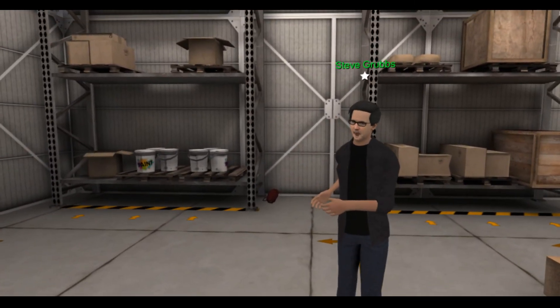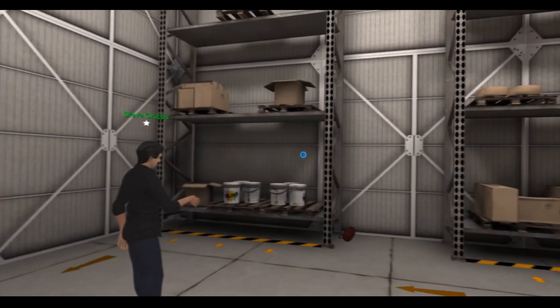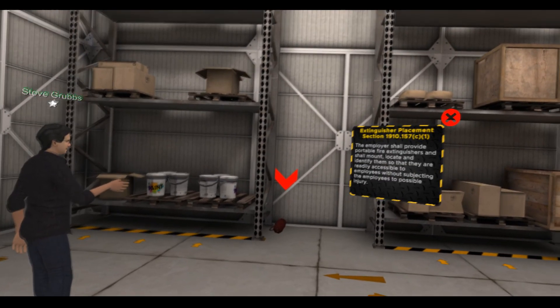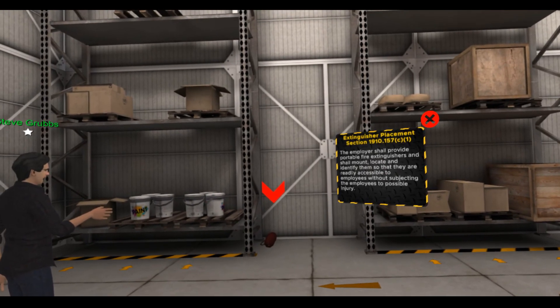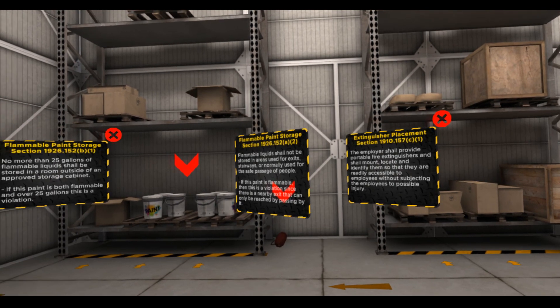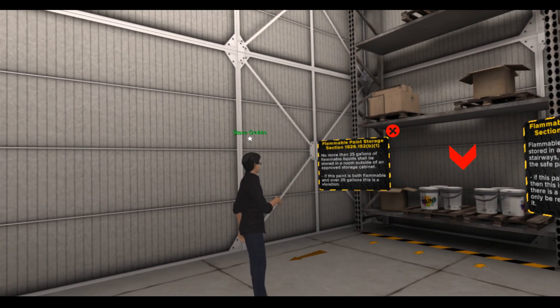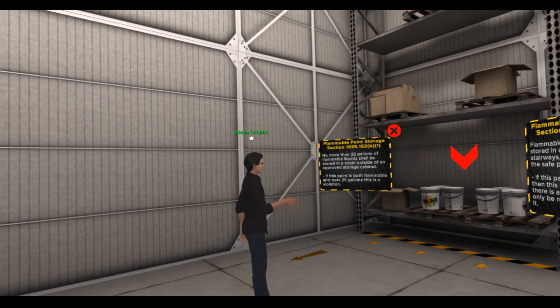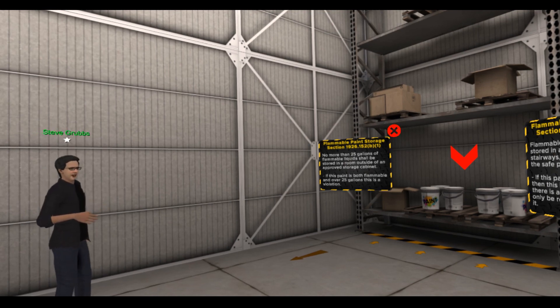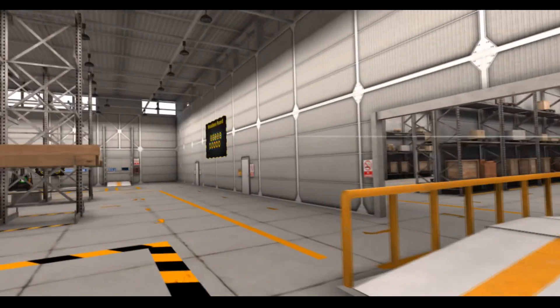We actually have a handful of problems over here. First, you'll notice this fire extinguisher on the ground — that is an extinguisher placement violation, which would be found by our firefighter who does training as well as an OSHA inspector. We also have a problem with this paint. There's a problem with our flammable paint storage that exceeds the limits on how much you can store together and how close it can be to a door. There are more violations around the building, and if we look at our scoreboard again, we'd see that they are scored right over there.